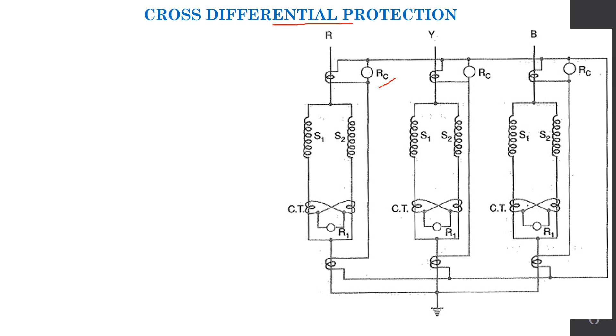Cross differential protection. Here, the relay RC is basically the Merz price protection relay. The relay RC will provide the protection against phase to ground and phase to phase faults, just like the Merz price protection. Whereas the relay R1 will be providing the protection against inter-turn faults. Here also, the CT is connected across the double layer winding of the alternators.